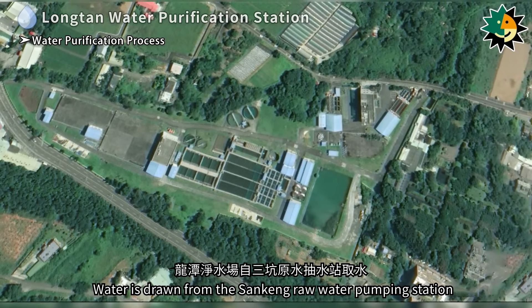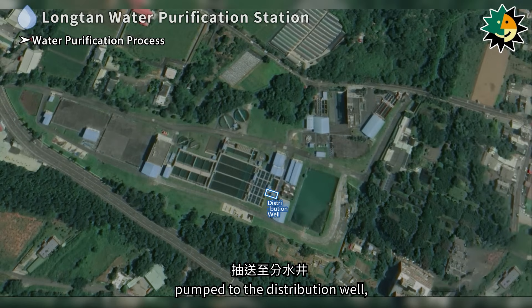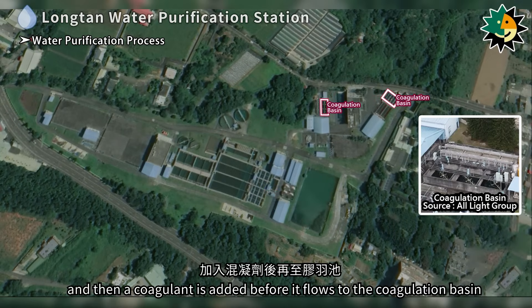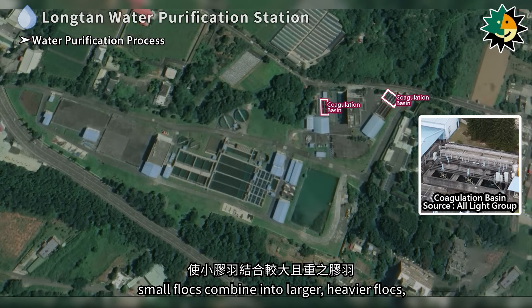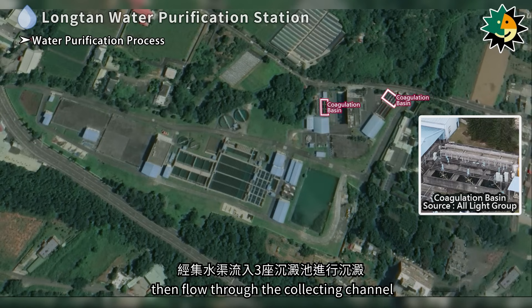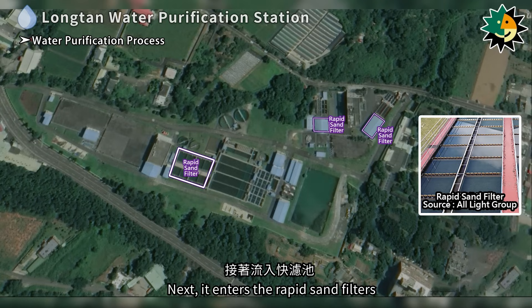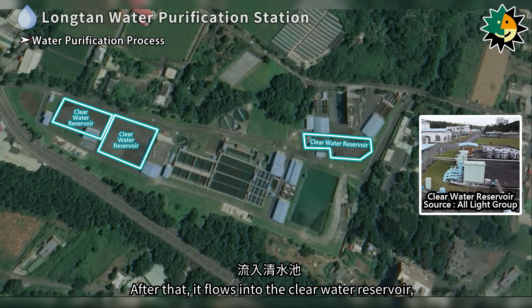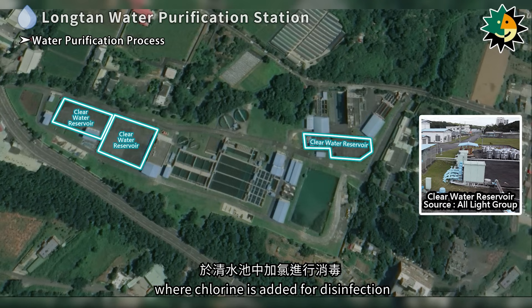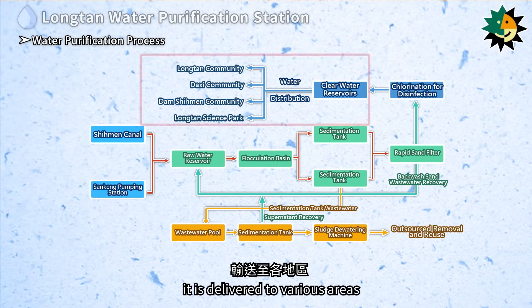Water is drawn from the Sankeng raw water pumping station to the Longtan water purification station, pumped to the distribution well, and then a coagulant is added before it flows to the coagulation basin. Through stirring by the flocculator, small flocs combine into larger, heavier flocs, then flow through the collecting channel into three sedimentation tanks for settling. Next, it enters the rapid sand filters to filter out small impurities and microorganisms. After that, it flows into the clear water reservoir, where chlorine is added for disinfection, and is delivered to various areas through the Longtan and Daxi water distribution systems.